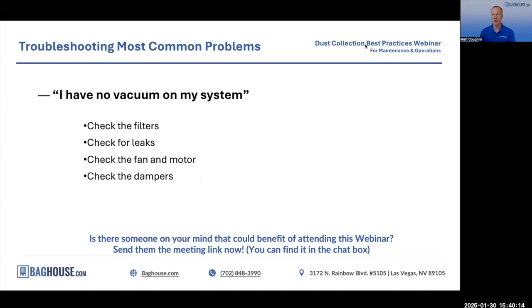Usually that's not the sole problem, unless you are talking about removing entire branches and leaving branches open to atmosphere, which we do sometimes see. So you want to minimize those leaks in your system. Go walk your ductwork, figure out where you may have air leaking, and fix it.